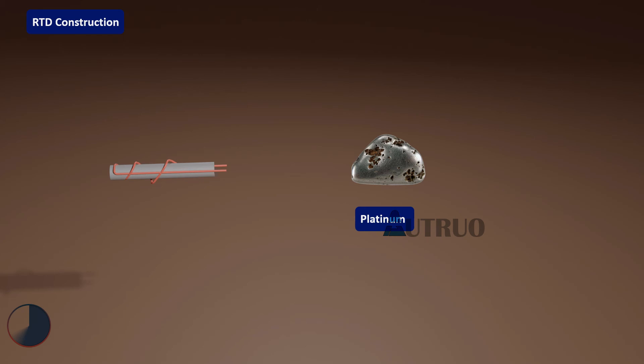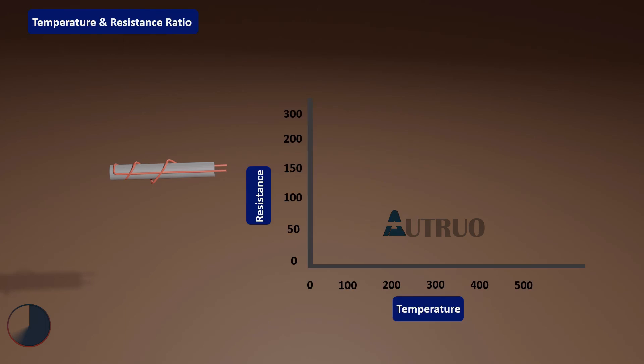In summary, at 0 degrees, PT100 ohmic resistance is 100 ohms. However, at 100 degrees, the PT100 resistance is 138 ohms.